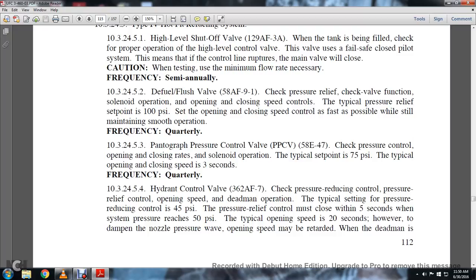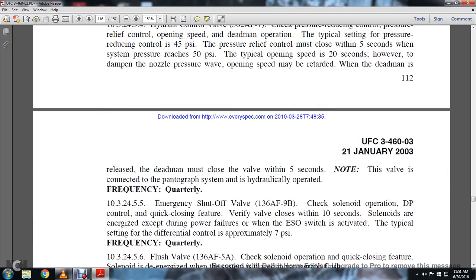Hydrant control valve: check the pressure reducing control, the pressure relief control, operating speed, and dead man operation. The typical setting for the pressure reducing control is 45 psi. The pressure relief control must close within 5 seconds when the system pressure reaches 50 psi. The typical opening speed is 20 seconds. However, to dampen the nozzle pressure wave, the operating speed may be retarded. On releasing the dead man, the valve must close within 5 seconds. Note the valve is connected with the pantographic system. It's hydraulically operated. Inspection frequency is quarterly.